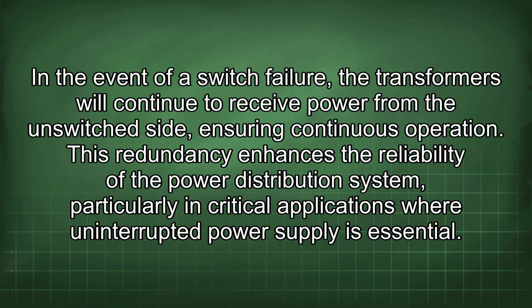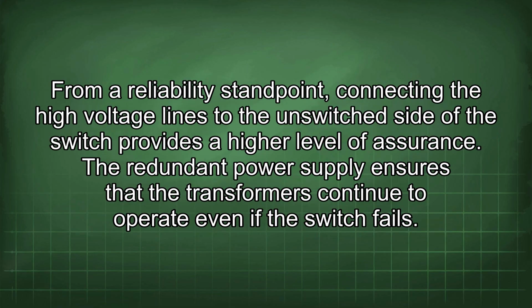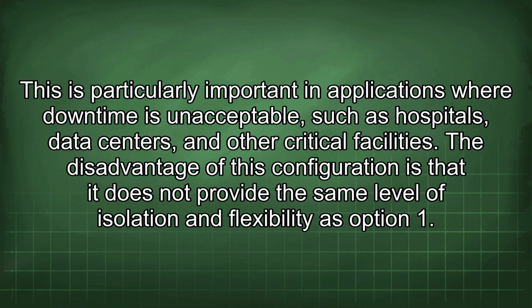A key advantage of this approach is that it provides a redundant power supply to all transformers. In the event of a switch failure, the transformers will continue to receive power from the unswitched side, ensuring continuous operation. This redundancy enhances the reliability of the power distribution system, particularly in critical applications where uninterrupted power supply is essential. From a reliability standpoint, connecting the high-voltage lines to the unswitched side of the switch provides a higher level of assurance. The redundant power supply ensures that the transformers continue to operate even if the switch fails. This is particularly important in applications where downtime is unacceptable, such as hospitals, data centers, and other critical facilities.